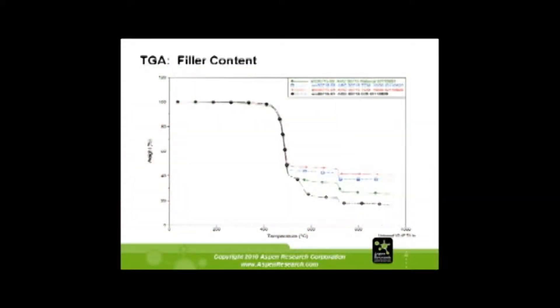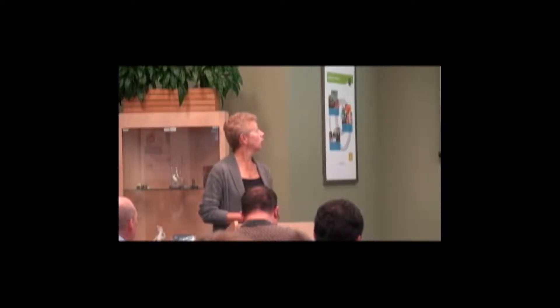Typical applications include thermal stability, compositional analysis, and oxidation stability. Now with some sample data — these were all supposed to be the same material. As you can see, the top portion of the curve, the polymer portion, is fairly much all the same — they are all on top of each other. But when you get to the inorganic portion of the sample, there is a huge difference. This one has about 20% inorganics and this one has about 45% inorganics, so you're going to have a totally different feel to those materials.